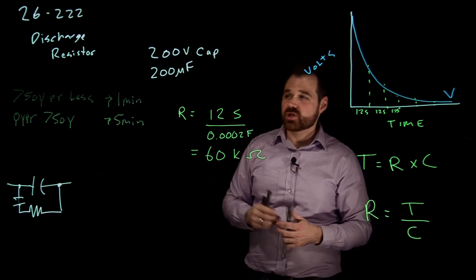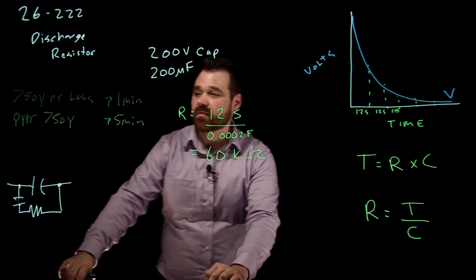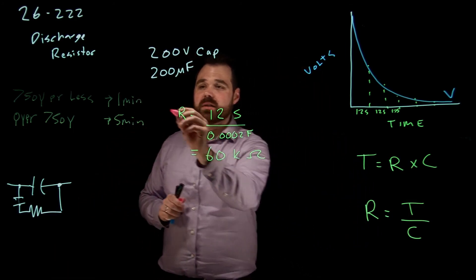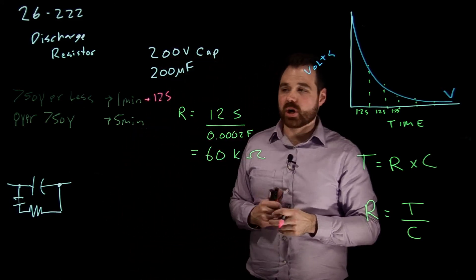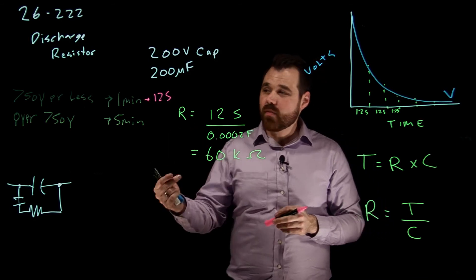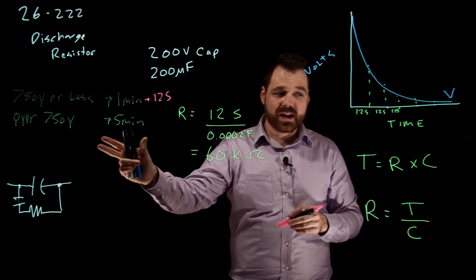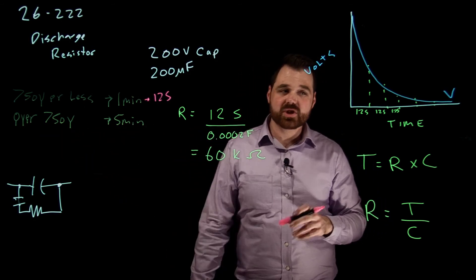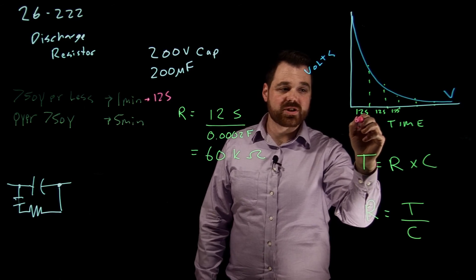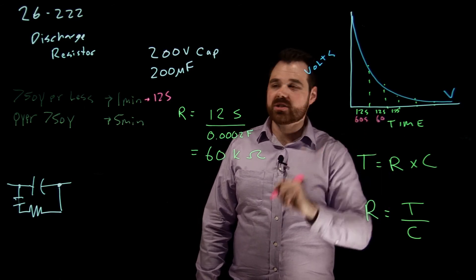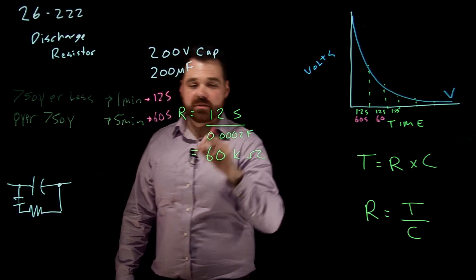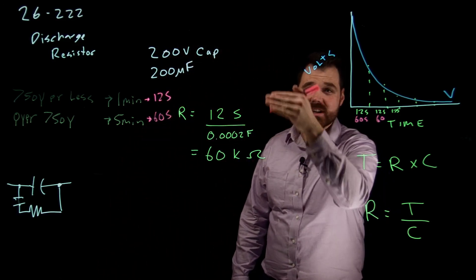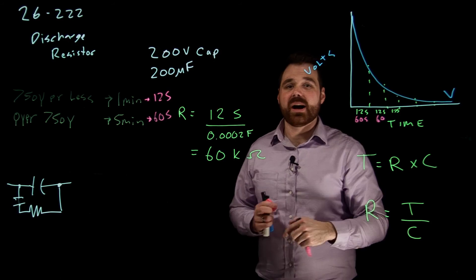Now how this would change - so if I'm talking 750 volts or less, and it's one minute, we say that's 12 seconds per time constant. If I was over 750 volts, and I had five minutes in order to discharge, now that would be 60 seconds per time constant. So I would just change this formula, and now it would be 60 divided by the size of my capacitor.